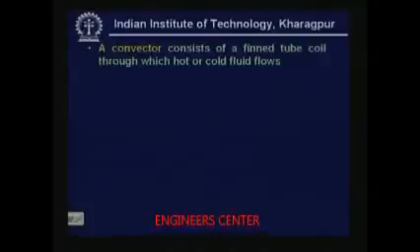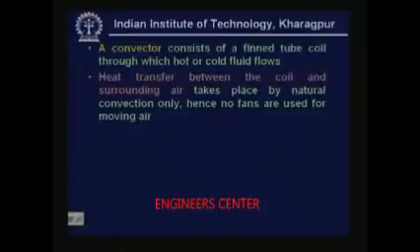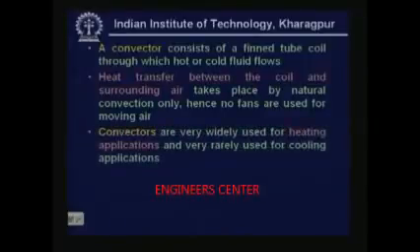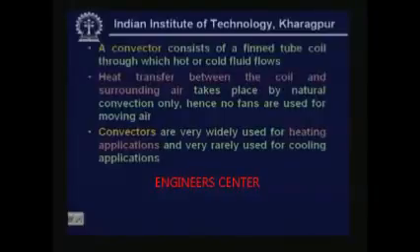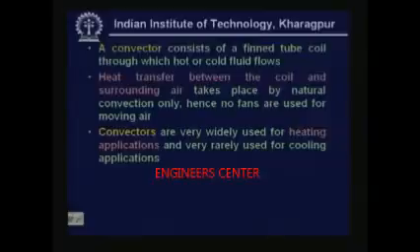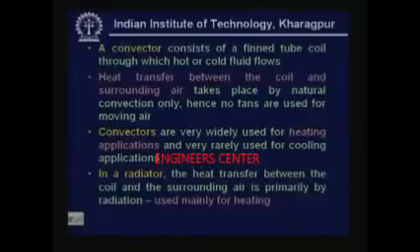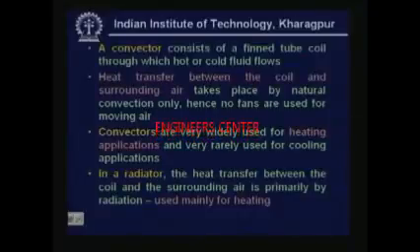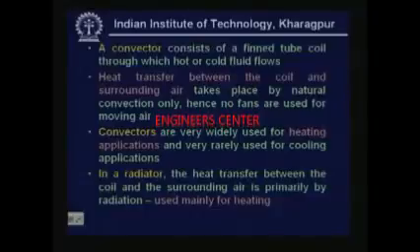A convector consists of a fin-tube coil through which hot or cold fluid flows, and heat transfer between the coil and surrounding air takes place by natural convection only — hence no fans are used. Convectors are very widely used for heating applications, but very rarely used for cooling applications, though sometimes they are used in cold storages. In a radiator, as the name implies, heat transfer between the coil and surrounding air is primarily by radiation, though there is also some heat transfer by natural convection. Radiators are mainly used for heating, though nowadays radiant panels are also used for cooling applications.